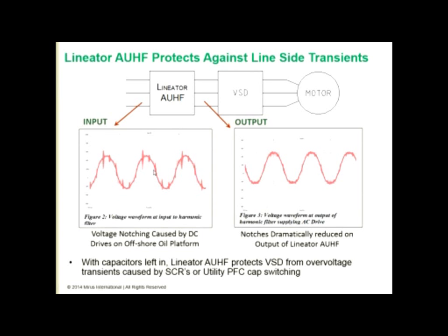So the graph on the left shows the voltage that was measured on the input of our filter. And we can see the overvoltage, the drop in voltage which is introduced by the rectifier, the overvoltage spike that we have with it, and then the ringing. And without the Lineator filter, the variable speed drive would see these overvoltage transients and this will cause the drive to trip out, or in severe conditions will cause components to fail. On the drilling rig, the drives were tripping out on a regular basis.